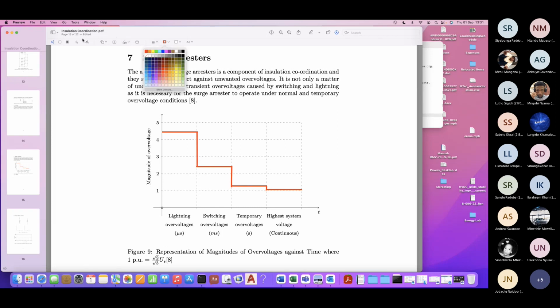Let me see if I can draw a curve. So, surge arrestor, you want it to operate for your lightning overvoltages and switching voltages. You want to cap your voltage here, and then you want to allow the normal operating voltages to work. So it must be an open circuit on the right, a short circuit on the left. Let's draw that in.